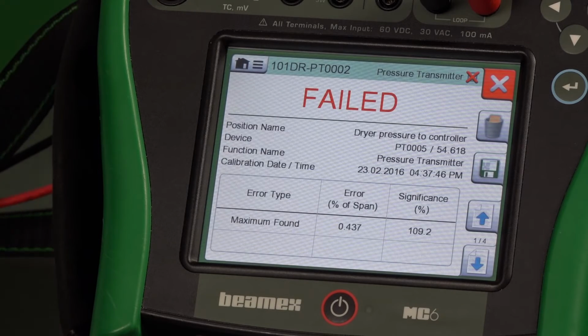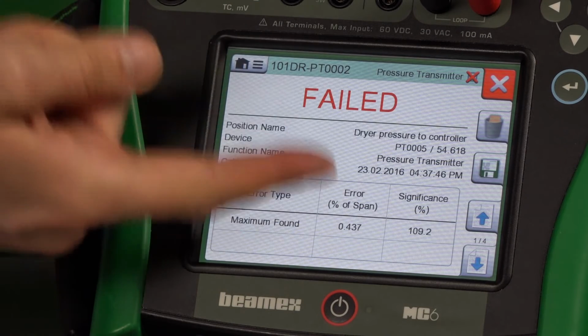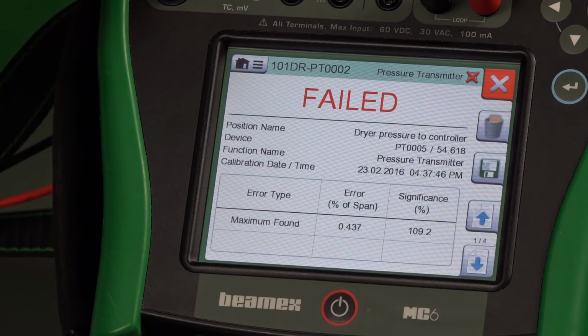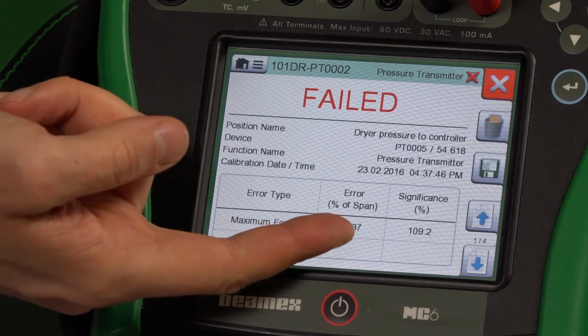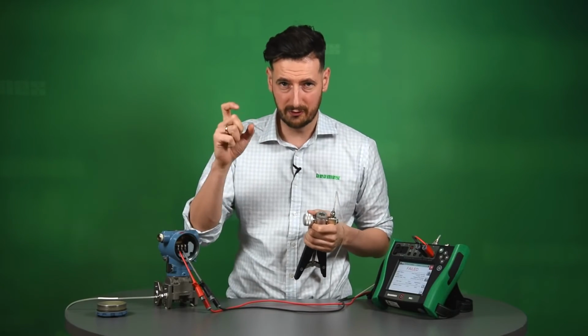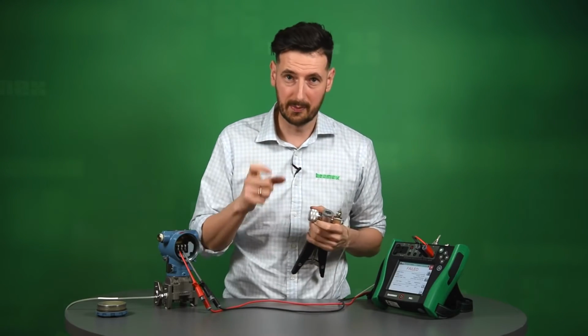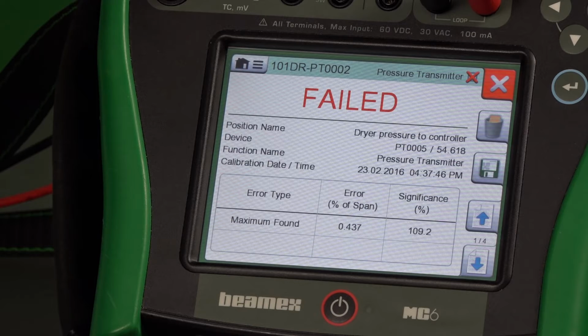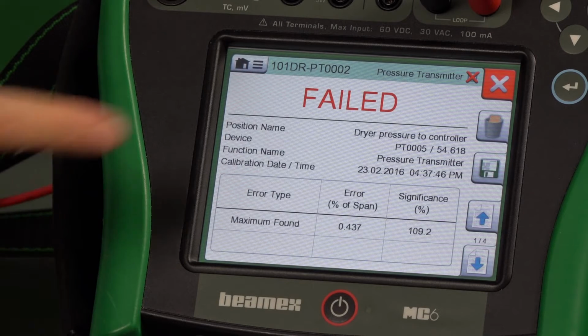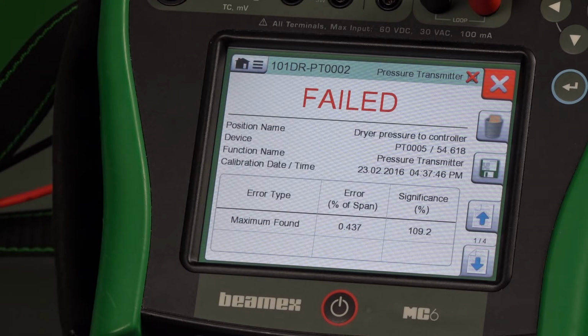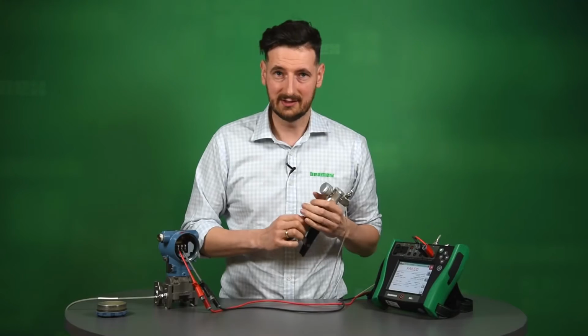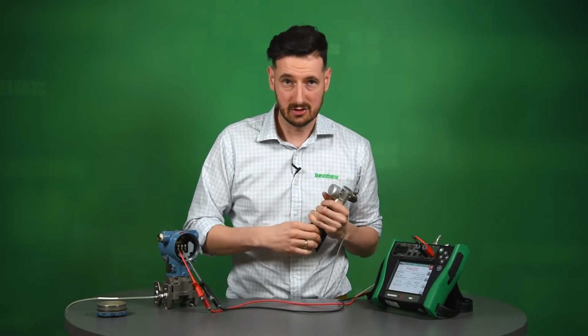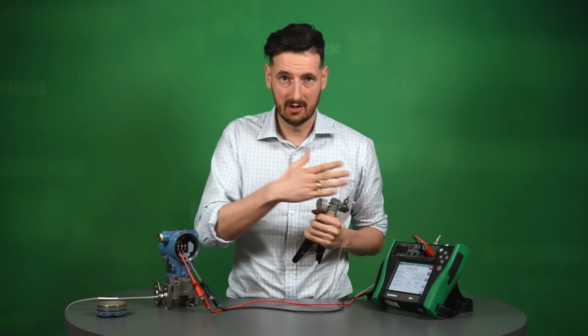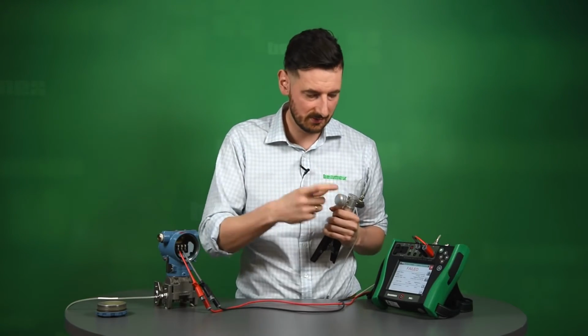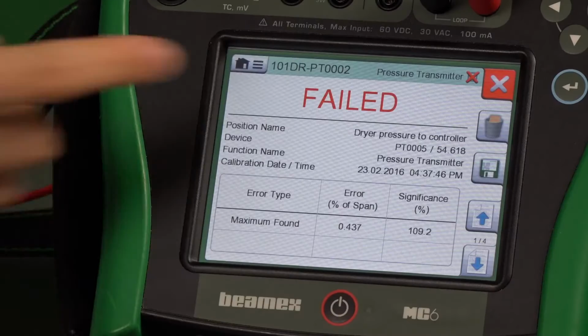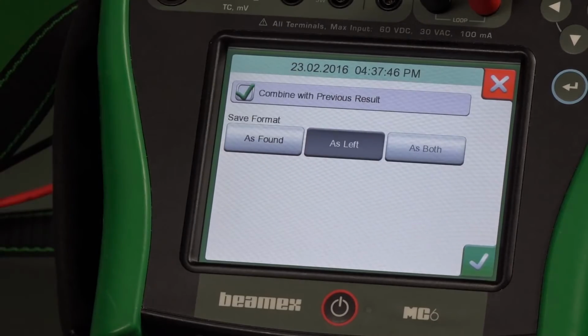It's saved the calibration, so it's sort of accepted the last point, and you can see what information we've got provided here. You remember our tolerance was 0.4% of span. We achieved 0.437, which is 110% significant error. This is probably, arguably, the most important information here on this screen. It tells us how far out we are. So sometimes it could be 70, 80, 90%, 100% is at tolerance. So you need to make sure you're always under 100% to have it obviously pass.